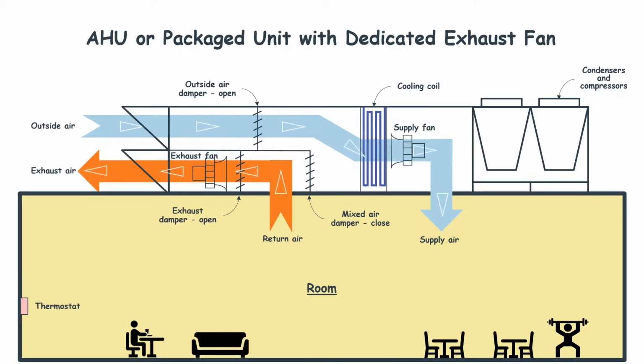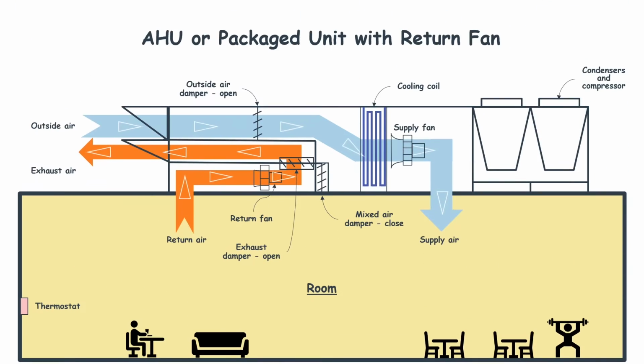Using a dedicated exhaust fan is the second method. In this method, an exhaust fan, which can be part of the air handling unit or package unit, starts to operate when the system goes into the economizer mode. By exhausting the room's air, this fan relieves the pressure from the room. The third method is changing the system's return air fan into an exhaust air fan. This method is only applicable to systems that have both supply and return air fans. In these systems, when the unit goes into the economizer mode, the mixed air damper completely closes and the exhaust damper opens. This turns the return air fan into an exhaust fan.